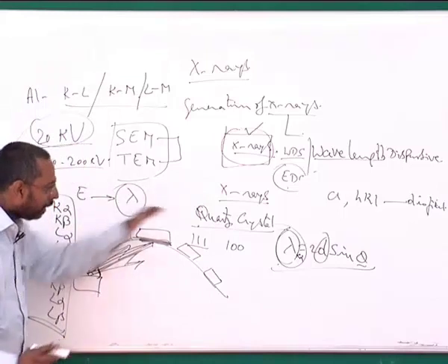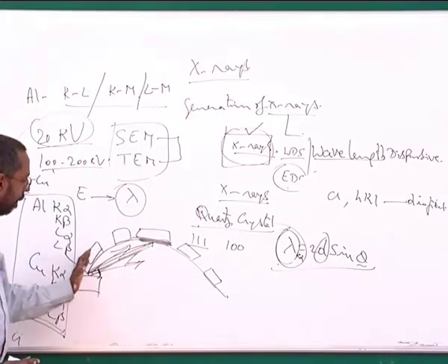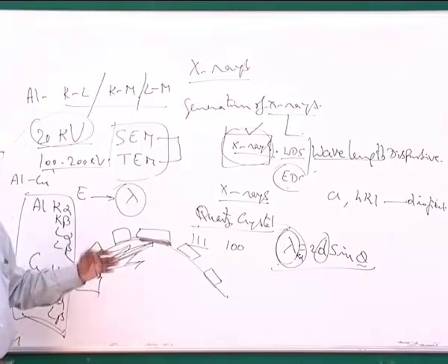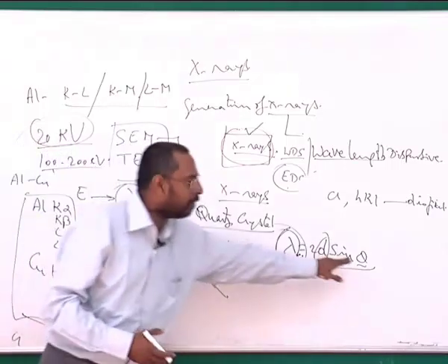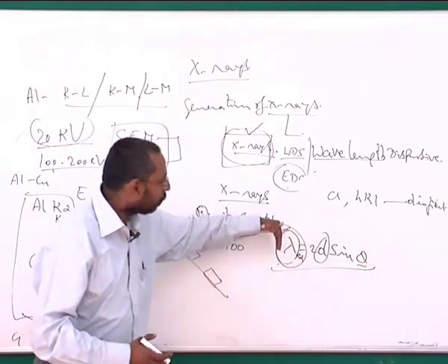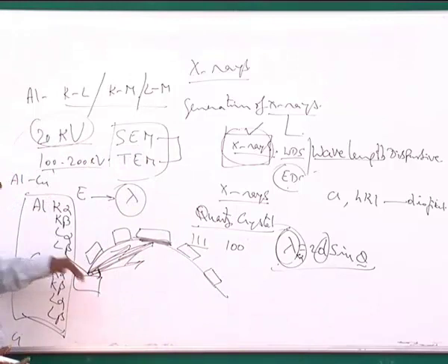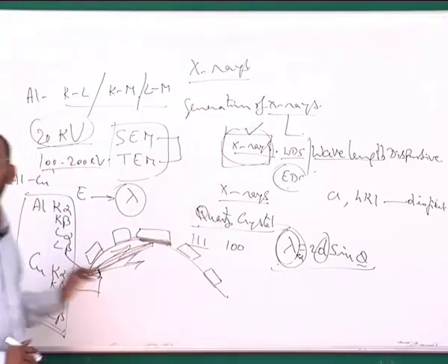I keep on rotating the single crystal along an arc, and at each place I hold it for a while to see if it is able to detect any one of these X-rays, because out of all these X-rays we do not know which are coming out and what the lambda of each is, and for every given lambda there is a certain theta. So the smaller the lambda, the smaller the theta. If I keep it at a small angle, it collects a particular lambda. If I keep it at a larger angle, it collects some other lambda.